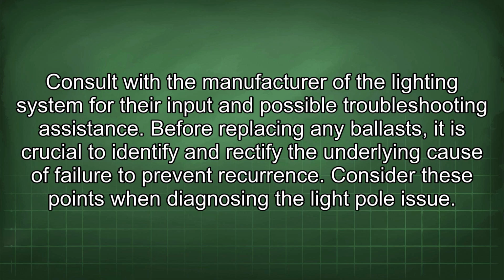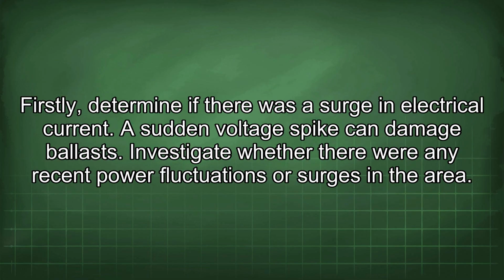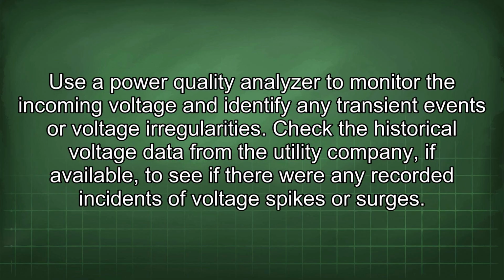Consider these points when diagnosing the light pole issue. Firstly, determine if there was a surge in electrical current. A sudden voltage spike can damage ballasts. Investigate whether there were any recent power fluctuations or surges in the area. Use a power quality analyzer to monitor the incoming voltage and identify any transient events or voltage irregularities.